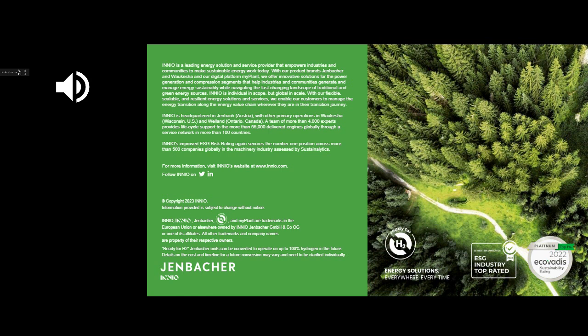Regarding efficiency, we're talking about the same efficiency levels, or pretty much the same, as a natural gas unit - efficiencies above 40%, around 43% for this unit. So although it has less power at the same rating, the overall efficiency is the same.